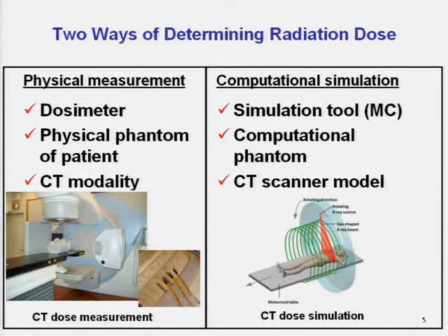And that's great. That's as good as you get. You know exactly what the dose is because you've measured it. But that is not a very robust process in that it applies only to that very specific scan that you just performed on that very specifically shaped phantom. And it takes a lot of time, and it takes time away from use of the machine, and nobody wants to be doing a lot of that. I think everybody would hopefully agree.